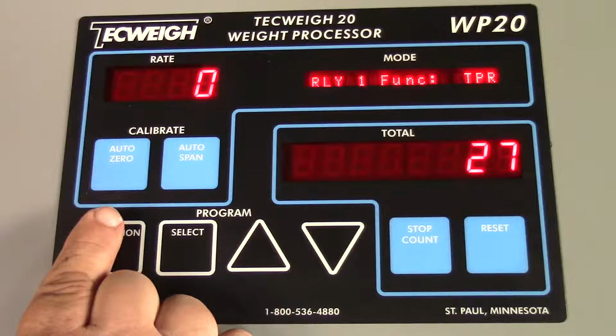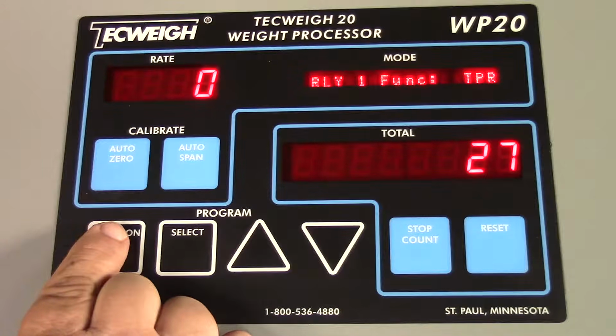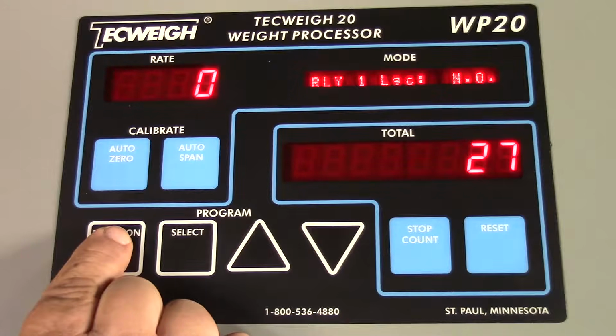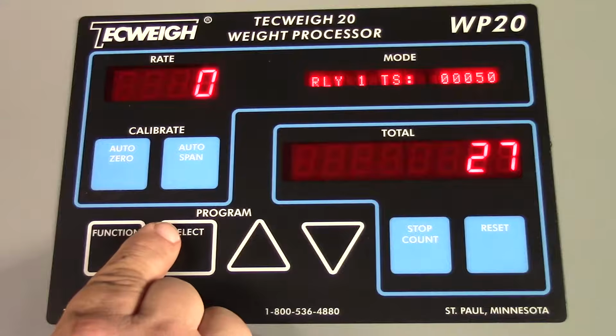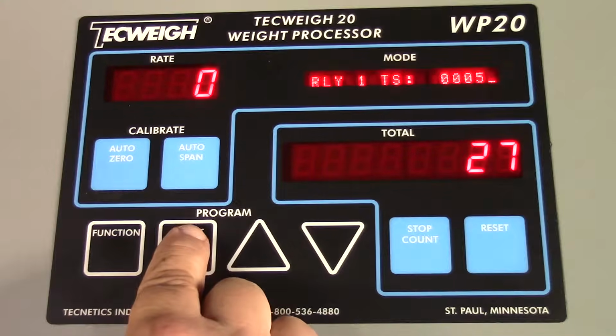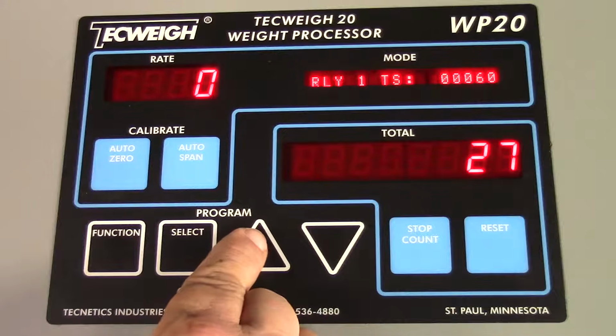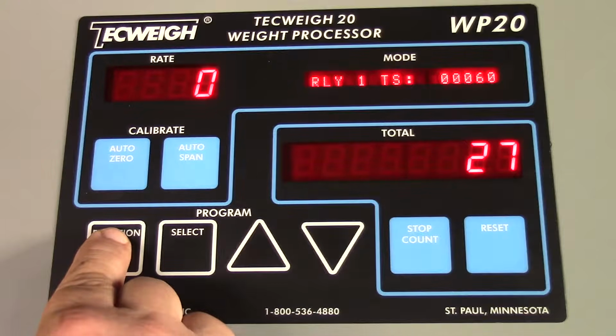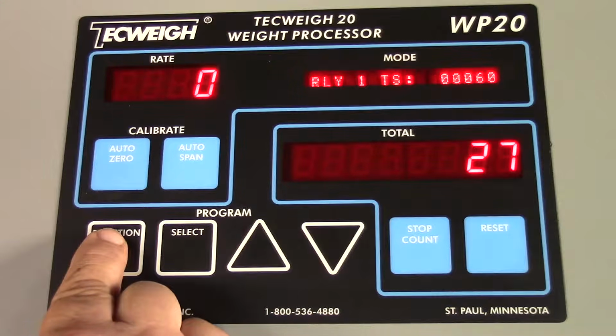Now here we can program one of the relays to function as a total pulse repeater. So that way every time the relay opens and closes, we know, for example, that like 1 ton has passed. And here in this parameter, we would set the pulse duration. That's the time for the relay to open and close. In this case, it's set at 1 second. And here we could set how many tons. In this case, it's 50 tons, but normally that's set at 1 ton. So for every 1 ton that passes, the relay will open and close, and you can count those pulses in the PLC. I just set it at 60.